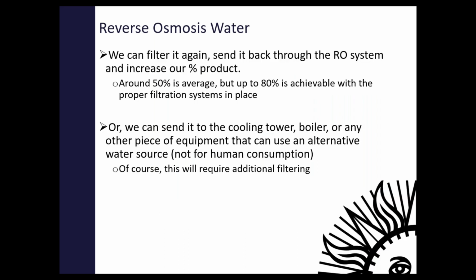So to improve that, you can just filter that concentrate stream again, send it back through your RO system. The consequence there is, of course, you're going to go through your RO membranes a little more quickly. Depending on the cost of those, you can weigh and see if it would be more efficient to save the water, or if it's better to just save on the membranes. And of course, you can send the concentrate somewhere else, use it for an alternative water source, but you do have to filter it and treat it before you send it into a mechanical piece of equipment like a boiler or a cooling tower, especially.